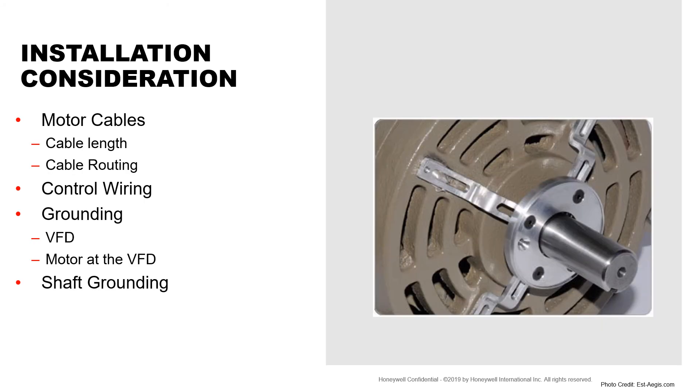The cables going to the motor should be kept as short as possible and not be run parallel with other cables. Follow the installation instructions provided with the drive, but it's generally best to keep the motor cables to less than 150 feet and separate it from parallel power or control cables.